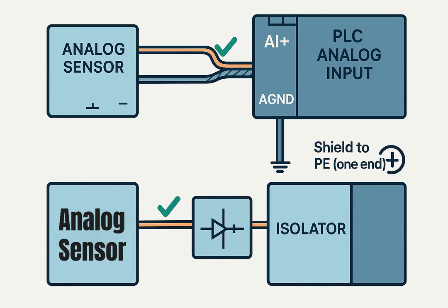In some cases, even when you wire to AGND correctly, the signal is still at risk or very noisy. For example, measuring from another remote system with a different ground reference, connecting to old equipment where the frame may leak current, or very noisy environments with large VFDs or induction furnaces. In these situations, use a signal isolator. It breaks the direct electrical path between sensor and PLC, and transfers the analog value through transformer, optical, or capacitive coupling. If a ground fault or large potential difference appears, it helps protect the PLC. But remember, on the PLC side, the output of the isolator must still be referenced to the PLC's analog GND, not to the PE bar.